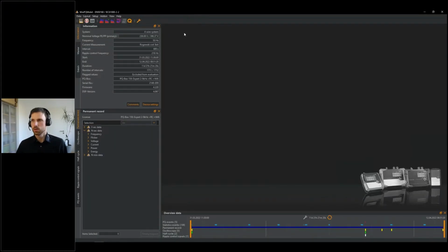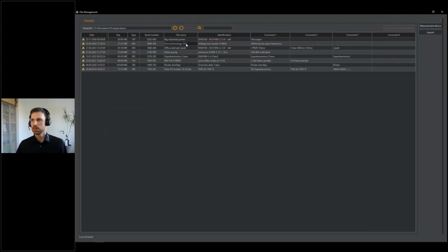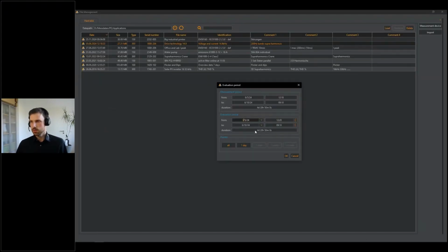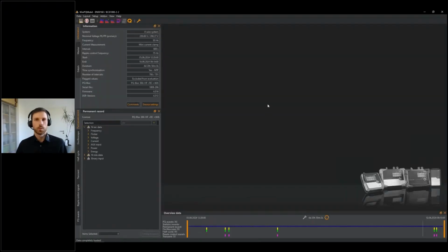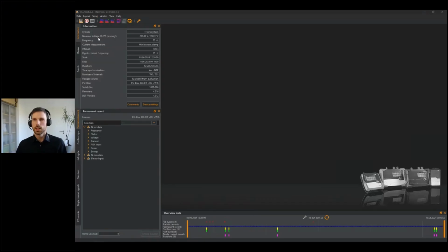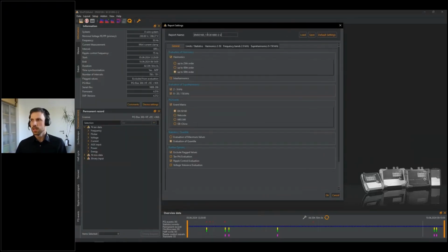PQ-Mobil. So now you see my screen, and I will open a measurement file. And here, this is only 4 days and 20 hours long, so less than a week in this case. So I cannot select 1 week, 3 weeks, or 4 weeks. But I go for all and confirm with OK. So first of all, I will check my report settings. Usually, PQ-Mobil, if you haven't changed any settings, goes with the default settings. And I go to Setup, Report Settings, and here we go. And this is the default setting.